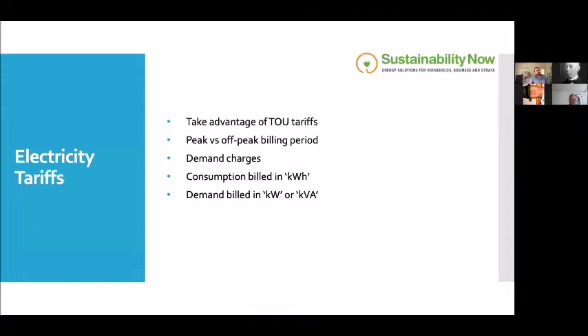In particular as well, you want to try and avoid your contractors who are doing routine maintenance and that sort of thing. Just make sure that they don't do any unnecessary testing of high power plant. So for example, your car park exhaust fans or something like that during that peak billing period, 2 p.m. to 8 p.m. Monday to Friday. Otherwise, you're likely to max out your demand, your billed peak demand, and be stuck with that for a year. So yeah, that's an important one.